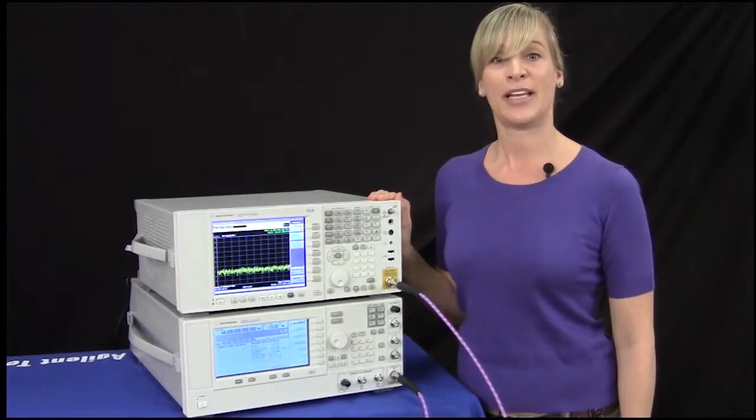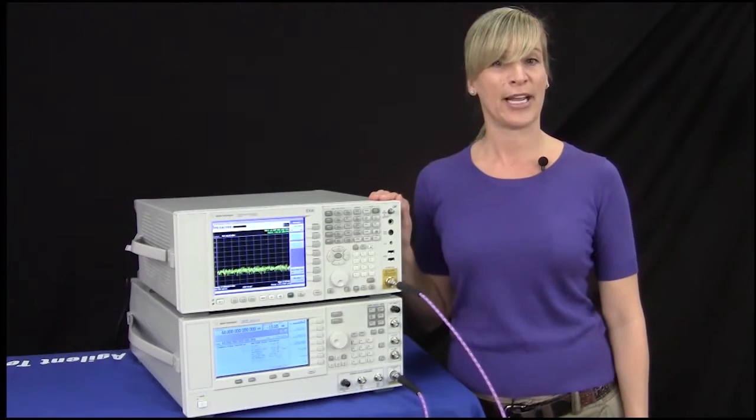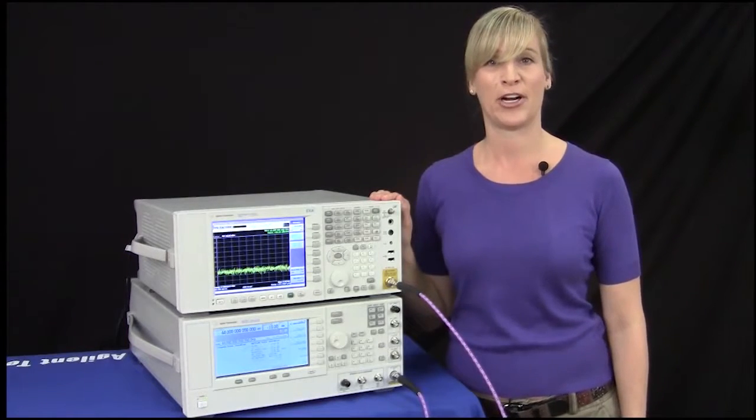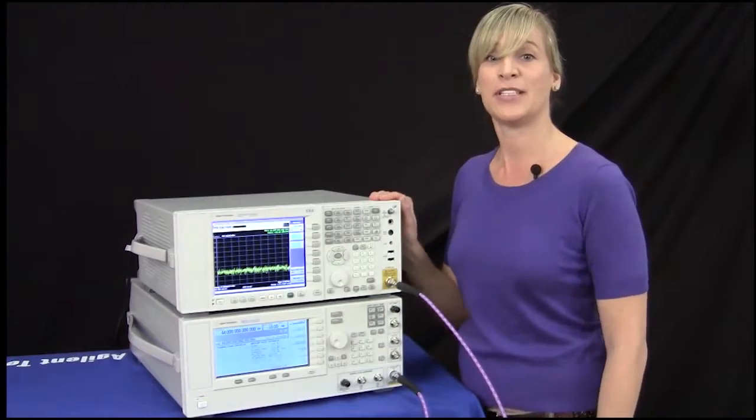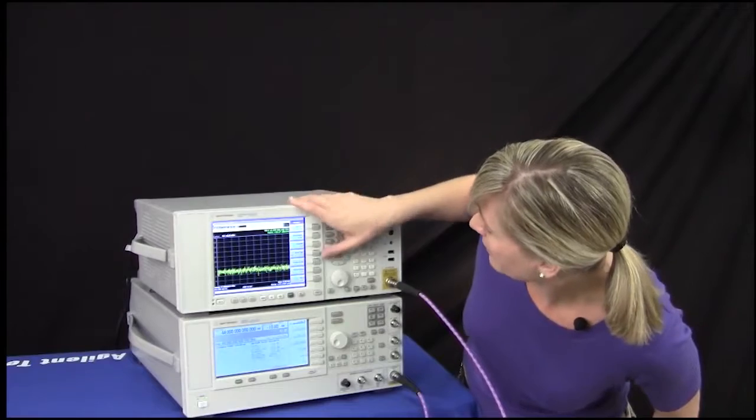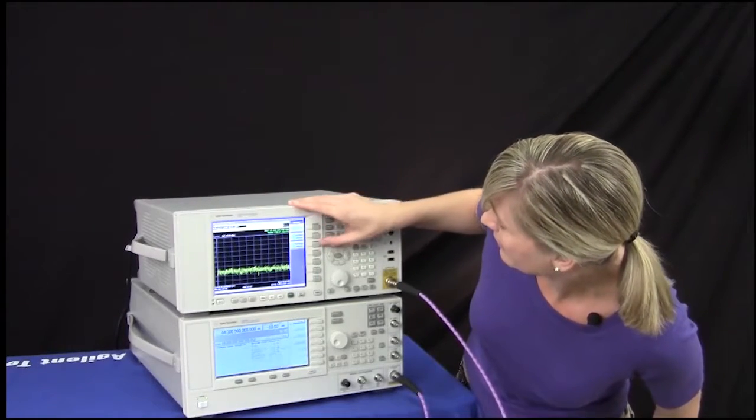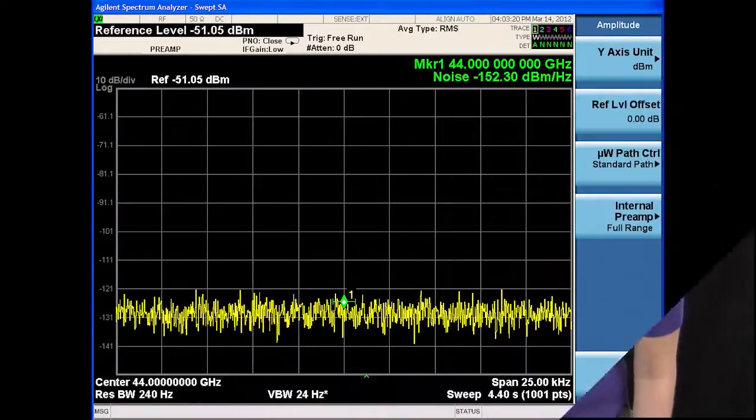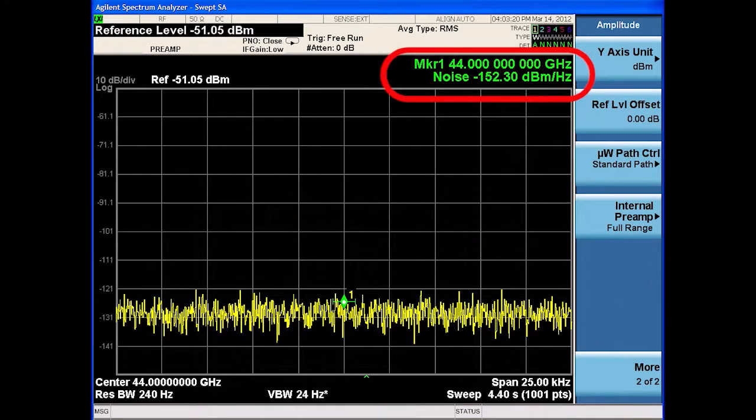The new millimeter wave EXA comes with a pre-amplifier option P44 that enables you to improve the sensitivity all the way up to 44 gigahertz. And now you can see that the noise floor performance of the new millimeter wave EXA at 44 gigahertz is better than negative 150 dBm per hertz.